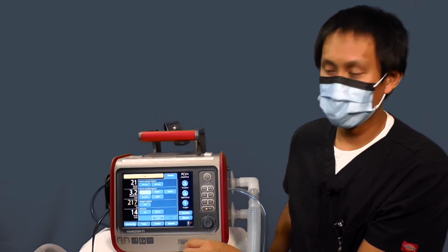So we're going to start with SIMV. You do have the capability of doing SIMV in volume or pressure. Most people are doing SIMV in pressure, so I'm going to select pressure SIMV, accept it, and these are the basic settings that come up. Just like before, your pressure inspiratory is a delta and not a total pressure. You do have flow trigger, and you do have the ability to sync your IMV on and off by checking the box. Under more settings, you do have PRAMP and your ETS and your side control. Typically we leave the PRAMP at the default and your ETS at the default as well. So once you're ready, you can hit confirm, and it seamlessly switches over to the other mode, as you can see at the very top left.